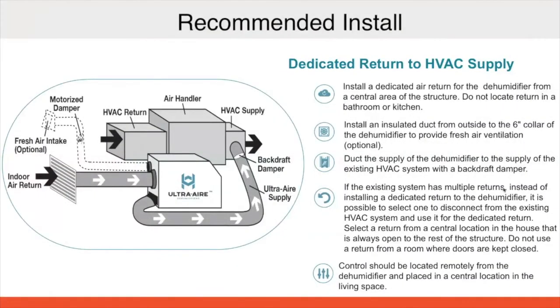So dehumidifier installs, our recommended install is a dedicated return to the dehumidifier, and then we're going to tie into the supply of the HVAC system. So this allows us to run the dehumidifier without ever running the fan on our air handler. So this is the most energy efficient way to set up a dehumidifier. And in our install instructions, we'll tell you exactly how to install these, the backdraft damper that you need installed there. But again, this is our recommended install.